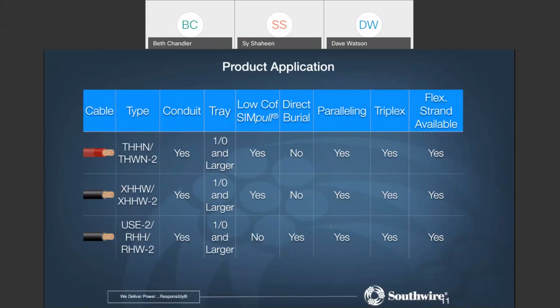Triplex is when at the factory, we actually cable or plex those conductors together. They're twisted together. So you're probably familiar with triplex and quadruplex products that are for service drop, or for underground service entrance. Also, if you look at the conductors inside of an MC cable or a tray cable type of construction, generally those conductors are going to be twisted or plexed together. So we can do that with these larger size products.